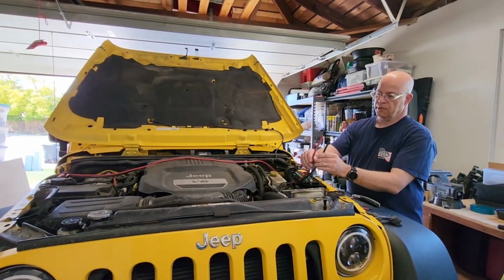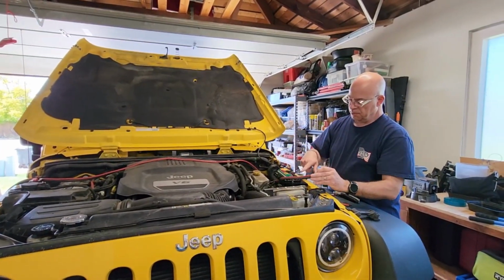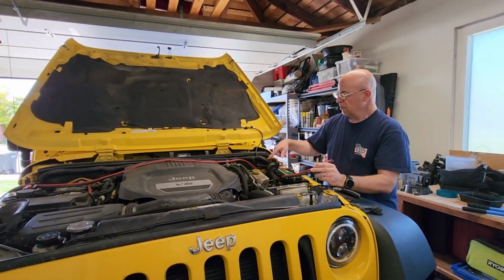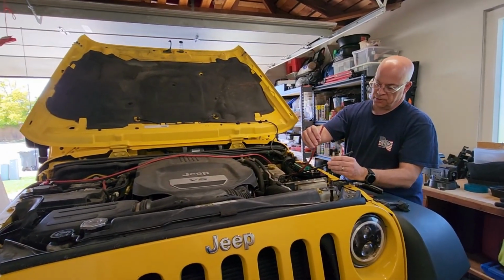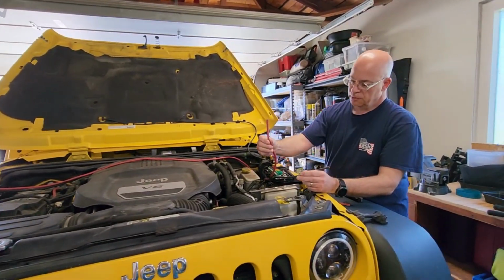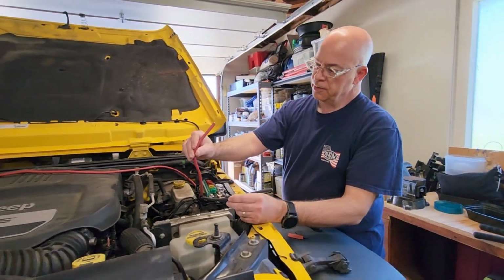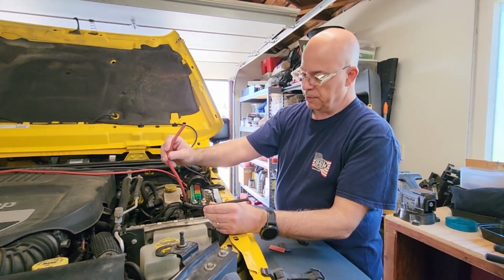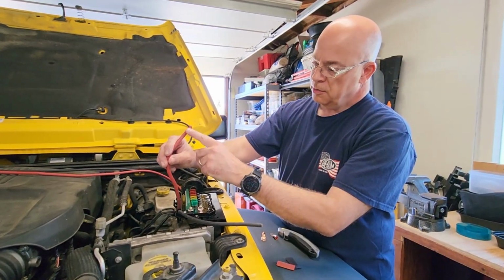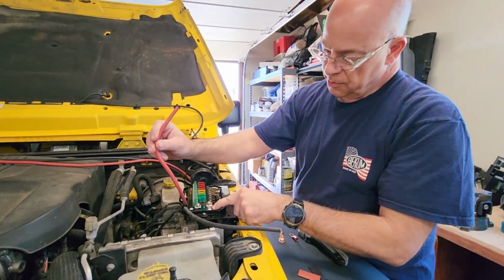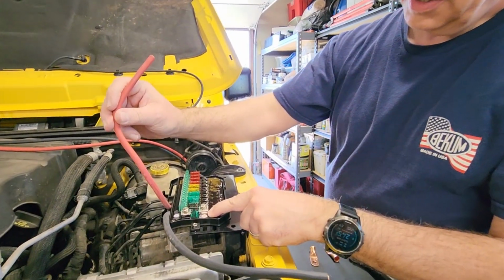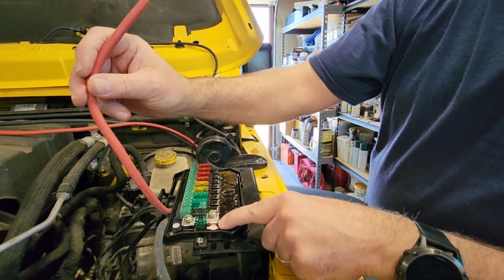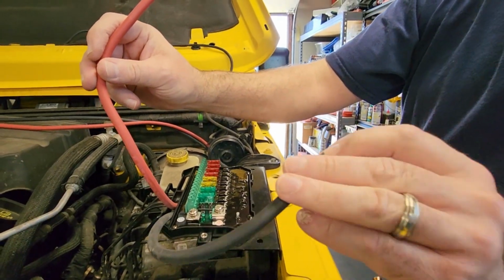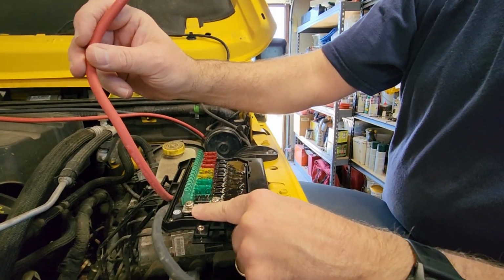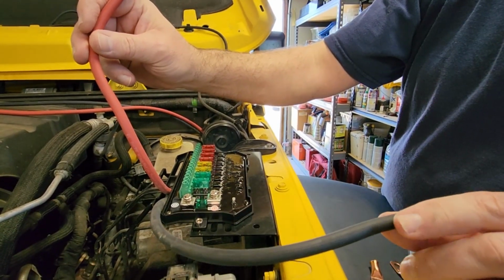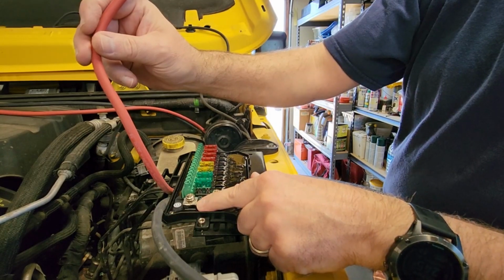Next thing we have to do is route battery cables from the relay panel over to the battery and the circuit breaker. We're going to use some other wire that didn't come with the kit because we've mounted it too far away. The red wire is going to go to the terminal that says plus, and the other side of the red wire will go to the circuit breaker. The black wire will go to the side that says minus, and the other end of the black wire goes to the negative terminal on the battery.